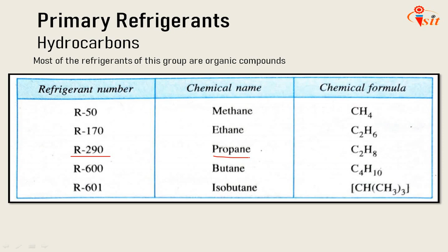Third category is the hydrocarbons. Most of the refrigerants of this group are organic compounds. Several hydrocarbons are used successfully in commercial and industrial installations. Most of them possess satisfactory thermodynamic properties but are highly inflammable. So some of the refrigerants are listed in the table here, that is R50, R170, R290, R600, R601. In the current scenario, R290 is a promising refrigerant which has a lesser ODP and GWP, or we can say approximately 0 ODP and GWP. It is propane, but the disadvantage is that it is highly flammable. Okay, so that is about the hydrocarbons.